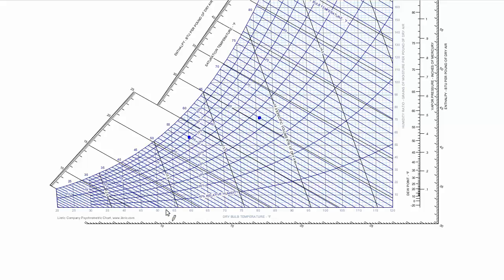When you're at the dew point, the dry bulb and the wet bulb temperature are the same. So you can look at 51 dry bulb and follow that up to 51 with 100% humidity and then follow that over horizontally.